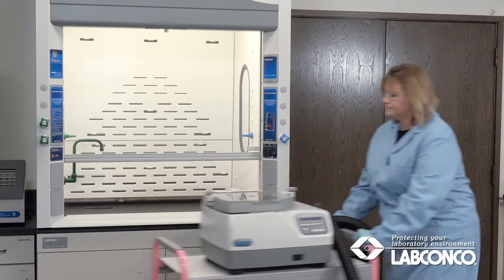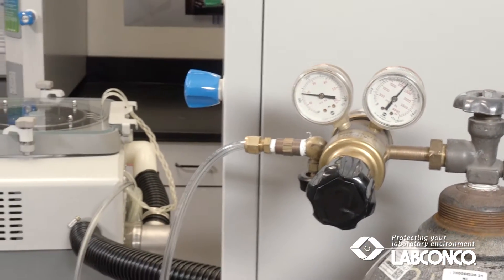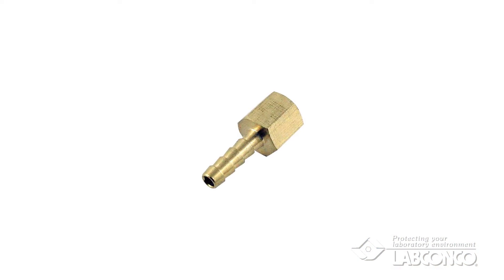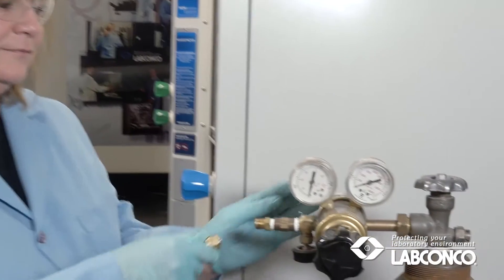Once the RapidVap is in place near a fume hood, the nitrogen will be connected. Install a barb fitting suitable for a 1/4 inch inside diameter hose into the out port of the regulator. Clamp it securely.